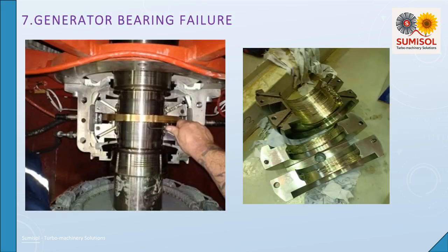The seventh and last case of this presentation video is related to a medium-duty generator bearing. The bearing shell was found with a complete lack of oil; the shell was dry, with steel dust. The white metal was completely worn out and the steel was also partially scratched. The fault affected the NDE sleeve bearing, causing high vibration, and after inspection the failure was observed. This failure was due to low oil level, while no further damage was found in other parts of the alternator such as the DE bearing and windings. It was concluded that the problem of low oil level was overlooked since all the tests were carried out at the factory with auxiliary power present, therefore the lubrication pump was always running on previous occasions.